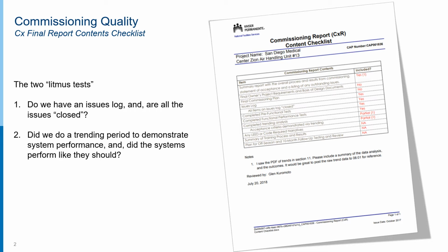And then the second question is, did all the issues on your issues log get resolved? Is there documentation that says every issue that came up got resolved? We want to make sure everything that's found not to be working winds up working before we close out the project. And then the third one is, did we do a demonstration period? So for HVAC systems, this is usually a trending period to demonstrate that the systems are working according to the design intent. And then finally, did those systems in fact work according to the design intent during that trending period? So those are the four questions that we asked. What I'm going to show you today is primarily an example of question 3 and question 4 about the trending period and working to the design intent.